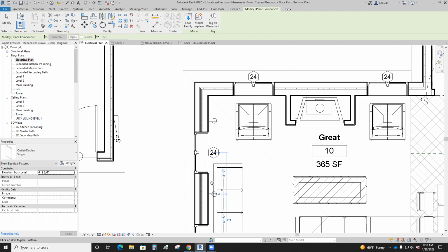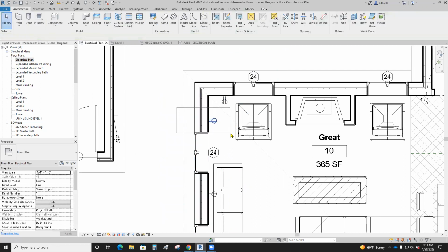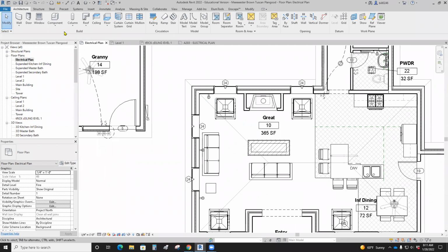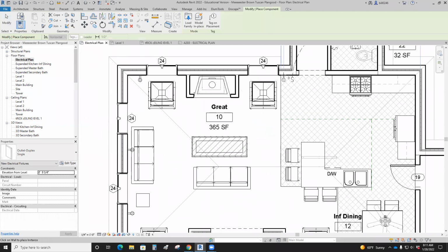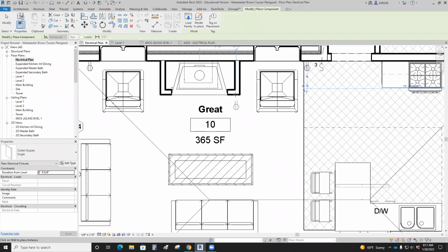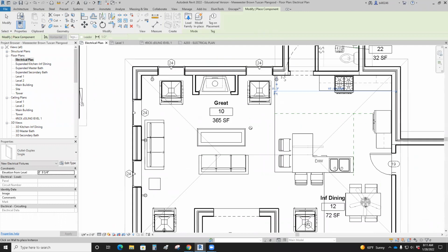Now, this one could have changed. Maybe I don't want one here. Maybe I wanted one on this wall instead because the 12-foot rule applies and I have no problem here, right? Because there's no way that that's 12 feet going linearly and turning the corner. Getting the rule, pretty straightforward. And then you just work it around and place the outlets. Common sense stuff, just places where you think it should be. Do you need one right here? Probably not. That's probably a crappy place for an outlet.